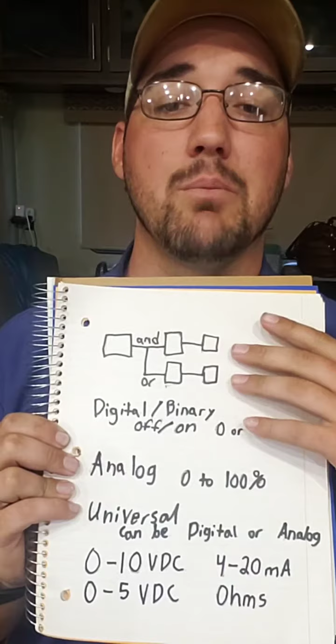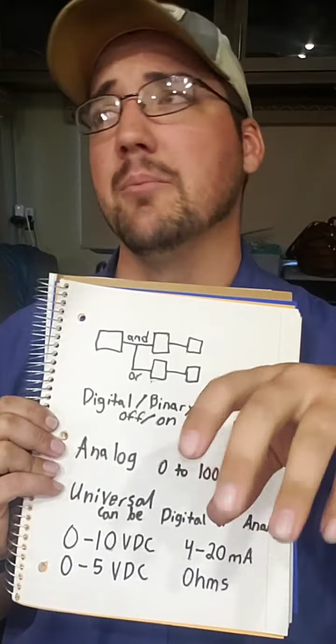So if you see an AI or an AO, that's what it's looking for. The thermistor and a transducer are going to be AIs. I mean, they're analog inputs, okay? An AO, the O meaning output, an analog output would be if you have an actuator. A perfect example, everyone I'm sure is familiar with, is Lennox package units. They've got their Prodigy controllers in there now, or they have had for some time. If you have an outside air package on that Prodigy system, it's going to have an analog output going to an actuator to open and close the outdoor air damper. Okay, that's an example of an analog output that you could run into.